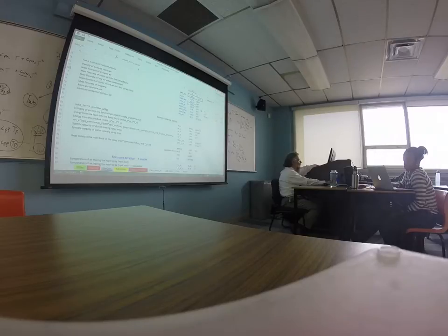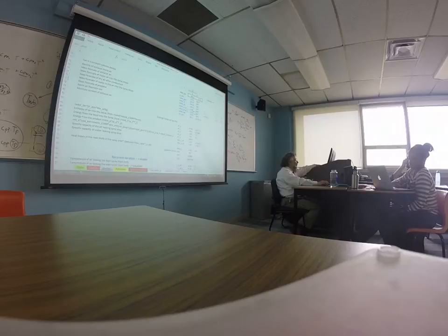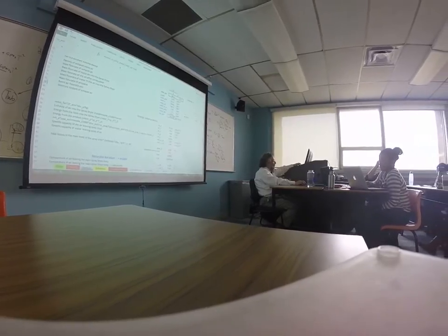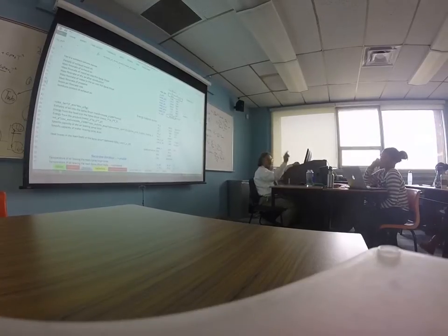And then the other calculations have to do with, if you take that and remove the water, then you get the dry air. That's one of the important things that we need to get. So the volumetric flow rate of dry air is very important for us, this mass flow rate of dry air after combustion. We call it dry air. That's very important because things are really referred to that number. Everything gets multiplied by that number. Then the mass flow rate of water that was going in, how much propane we used, how much air from the room, the moisture content. This is very important, the moisture content of the air going out, because that's the one that defines the final point.